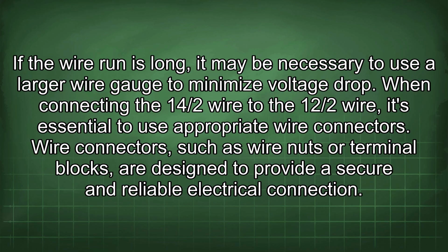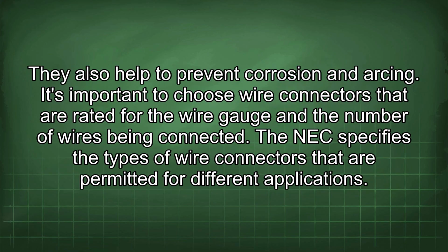When connecting the 14/2 wire to the 12/2 wire, it's essential to use appropriate wire connectors. Wire connectors, such as wire nuts or terminal blocks, are designed to provide a secure and reliable electrical connection. They also help to prevent corrosion and arcing. It's important to choose wire connectors that are rated for the wire gauge and the number of wires being connected. The NEC specifies the types of wire connectors that are permitted for different applications.